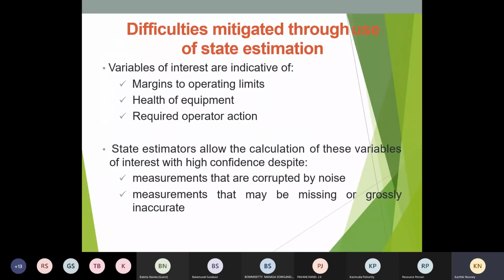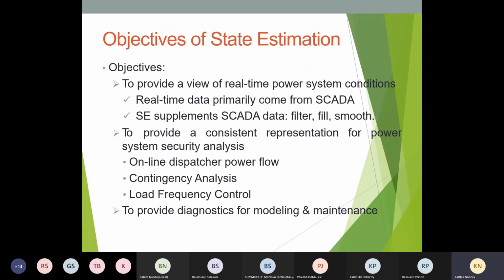So these difficulties are mitigated through the use of state estimation, because the variables of interest are indicative of the specific margins to operate within voltage limits, the condition of the equipment, we can say health of the equipment, and required operator action. These state estimators allow the calculation of these variables of interest with high confidence, despite measurements that are corrupted by noise and measurements that may be missing or grossly inaccurate. So we will go to the next slide.